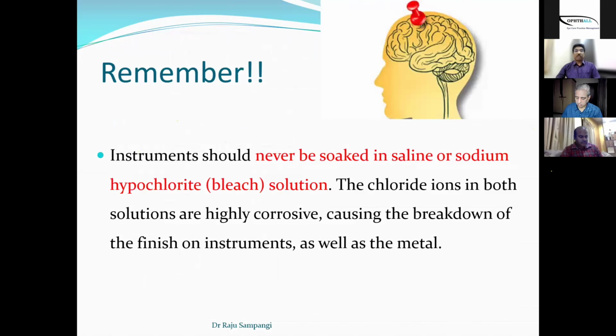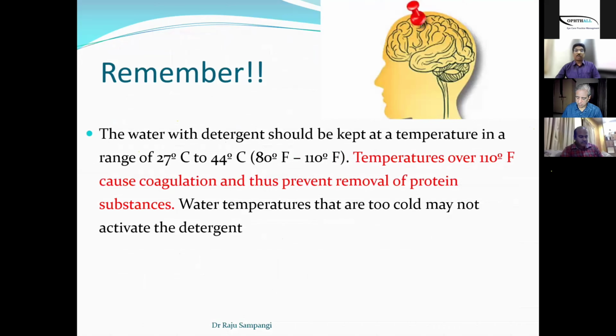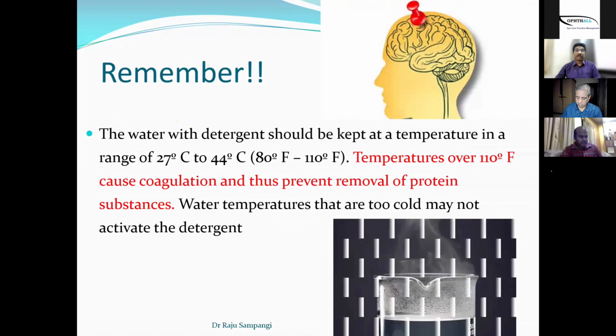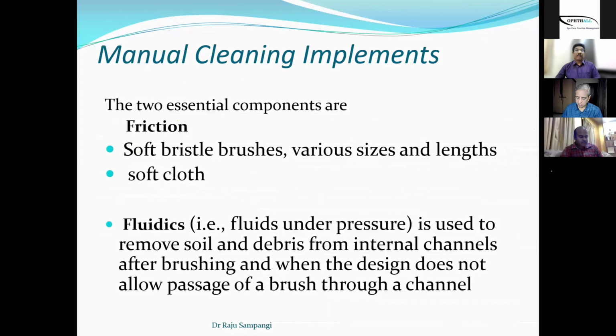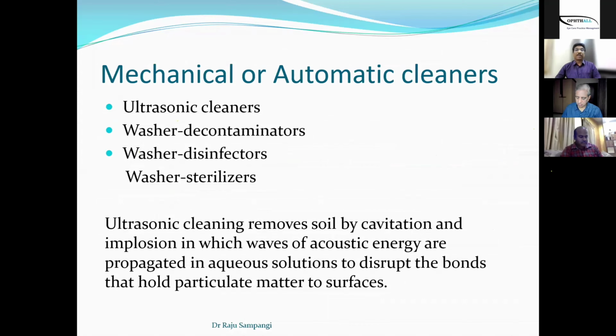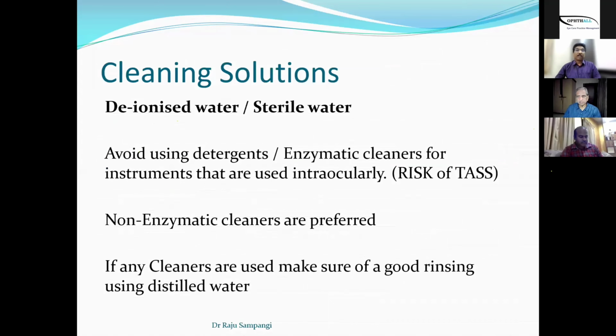You should remember that you should never soak the instruments in saline or sodium hypochlorite solution because the chloride ions are highly corrosive. And don't use hot water because it causes coagulation and prevents removal of protein substances. The various cleaning methods include friction and fluidics, or you can use mechanical and automated cleaners and also ultrasonic cleaners. The cleaning solutions and the water to be used is either deionized water, or sterile water would be better for the last wash.